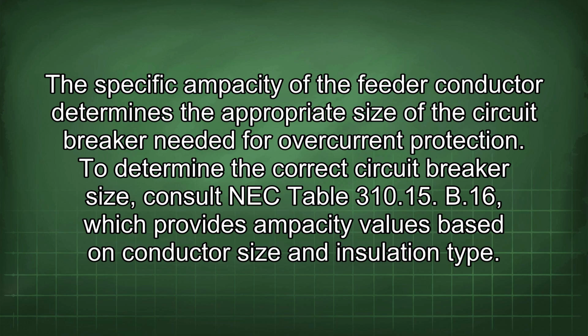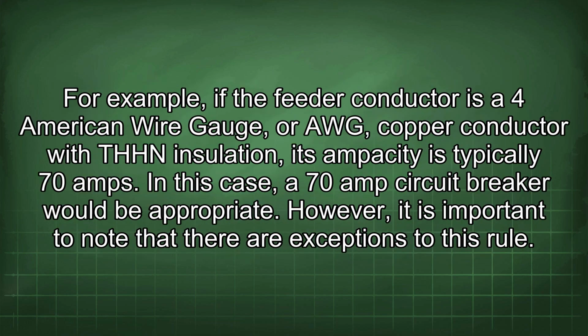To determine the correct circuit breaker size, consult NEC Table 310.15(B)(16), which provides ampacity values based on conductor size and insulation type. For example, if the feeder conductor is a 4 American Wire Gauge, or AWG, copper conductor with THHN insulation, its ampacity is typically 70 amps. In this case, a 70 amp circuit breaker would be appropriate.